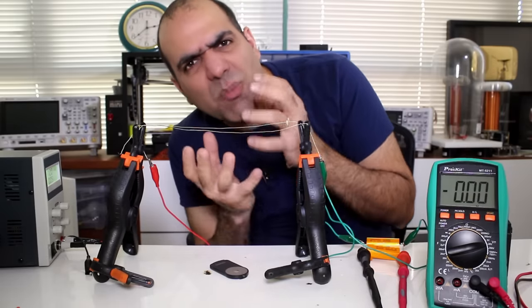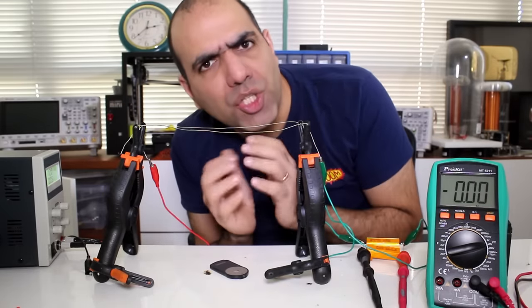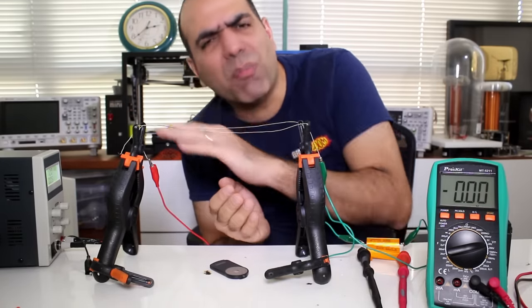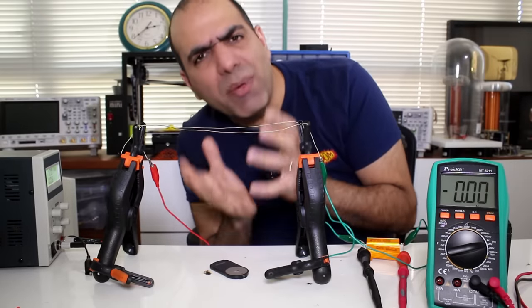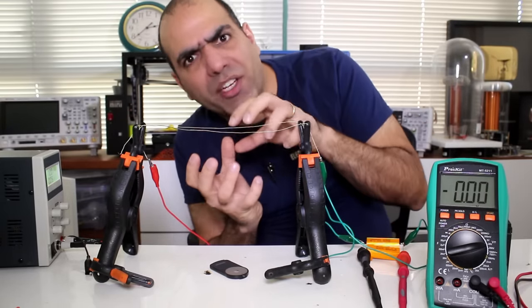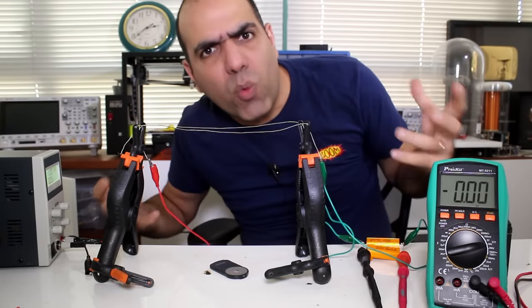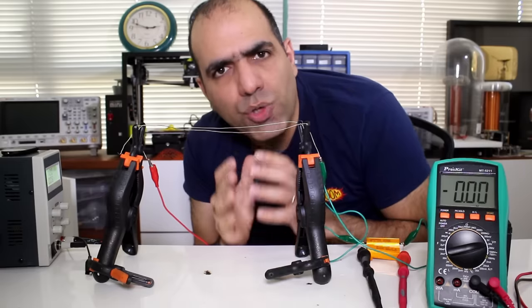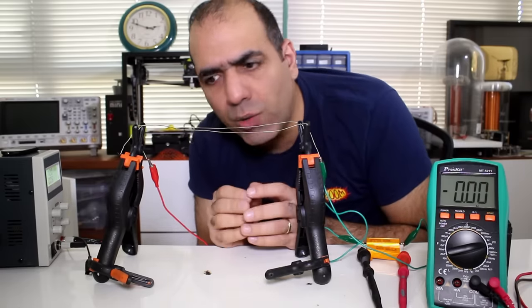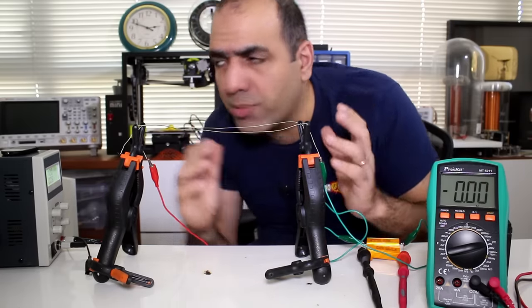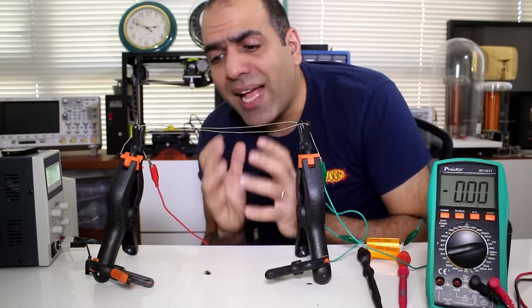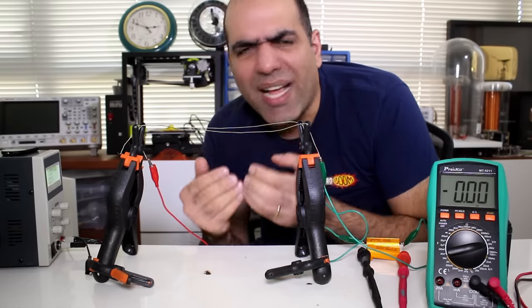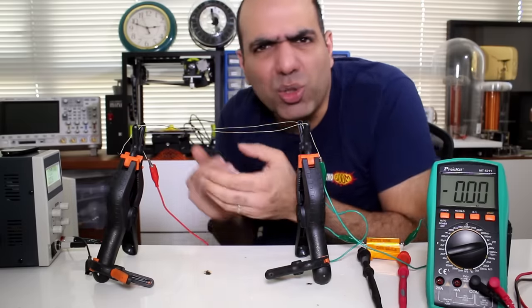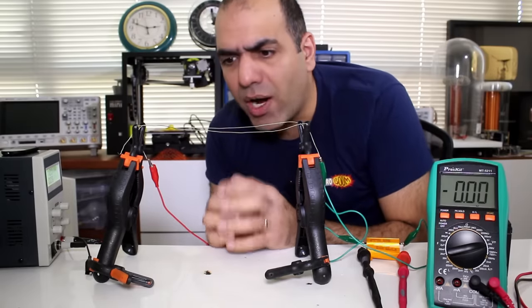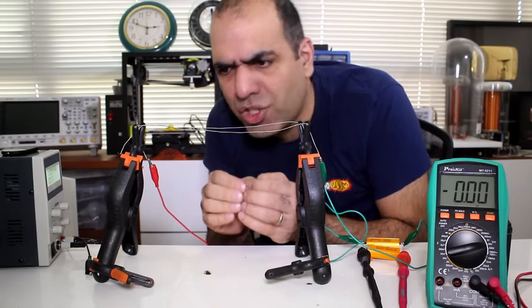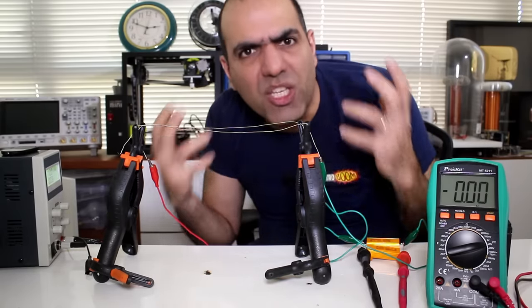Similarly, because Edison was passing low voltage across the transmission lines, a ton of current was passing through them. There's a limitation to how thick you can make the wires before they break under their own weight or become too expensive. Huge currents through the resistance of the wire would result in large voltage drops over longer distances. That's why Edison's system could only transmit power around a mile or two from the power source. Otherwise, the power loss over the lines would cause huge inefficiency.